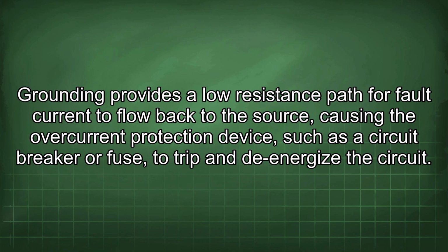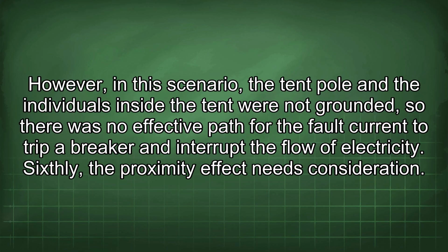Fifthly, the grounding concept is important. Grounding provides a low-resistance path for fault current to flow back to the source, causing the overcurrent protection device, such as a circuit breaker or fuse, to trip and de-energize the circuit. However, in this scenario, the tent pole and the individuals inside the tent were not grounded, so there was no effective path for the fault current to trip a breaker and interrupt the flow of electricity.